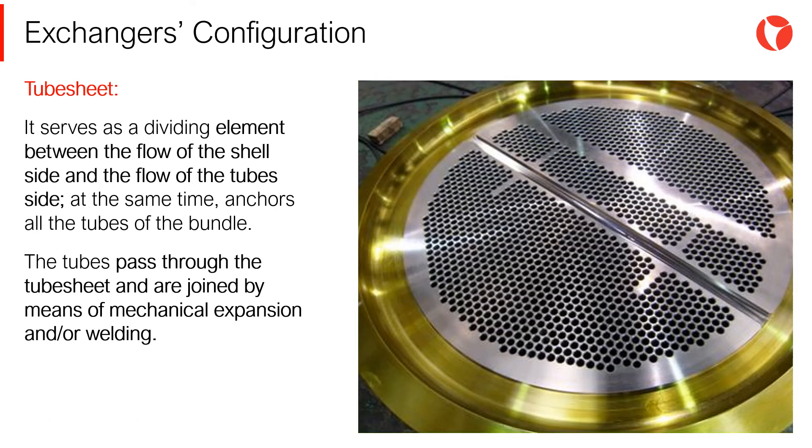The tube sheet is another key element of this type of equipment. It serves as a dividing element between the flow of the shell side and the flow of the tube side. At the same time, it anchors all the tubes to the bundle. The tubes pass through the tube sheet and are joined by means of mechanical expansion and/or welding.